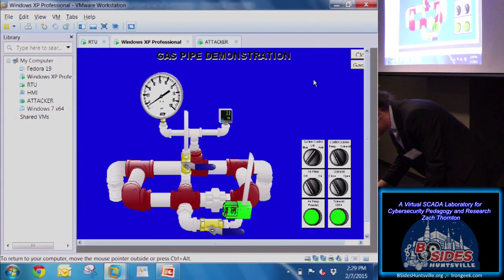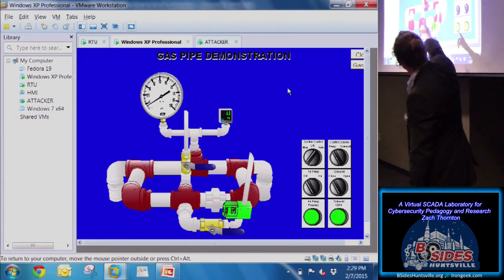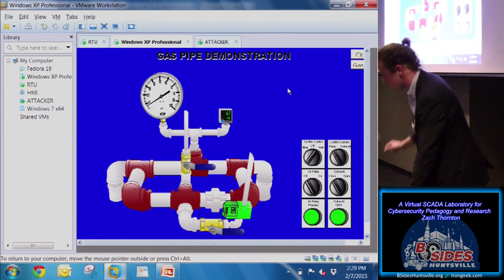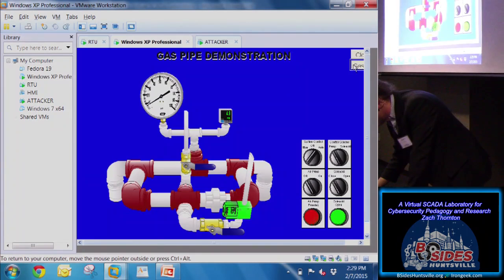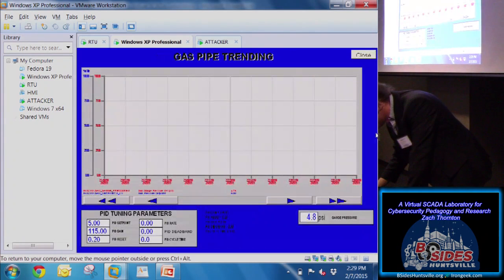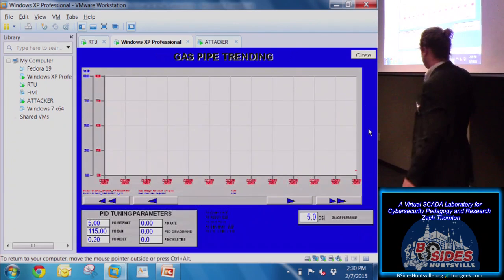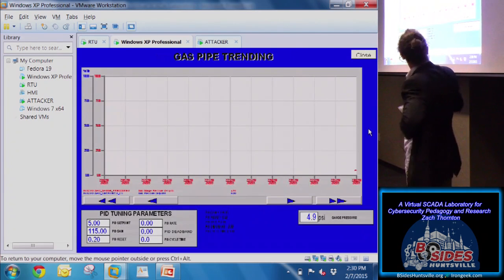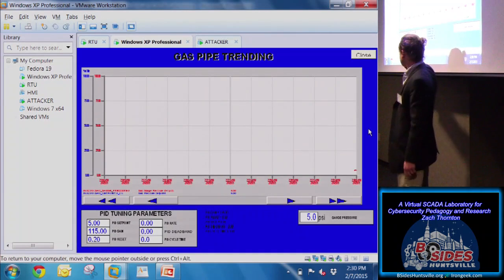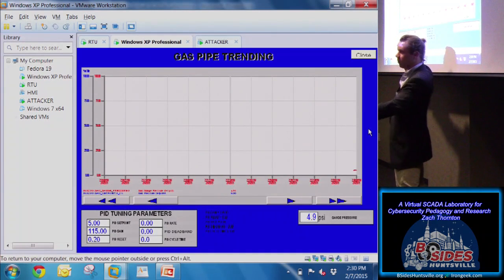You can see up here there's a pressure, but it's a lot easier to see if I bring it to this trend. In case I didn't explain it earlier, a lot of times pressure controls work by telling it a set point, the pressure you want. In this case, I've set it to 5 pounds.